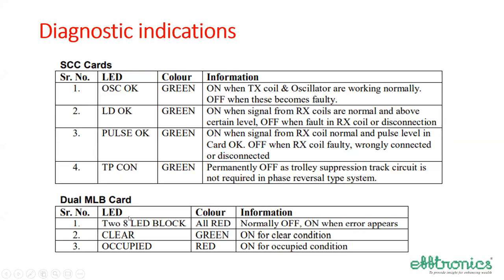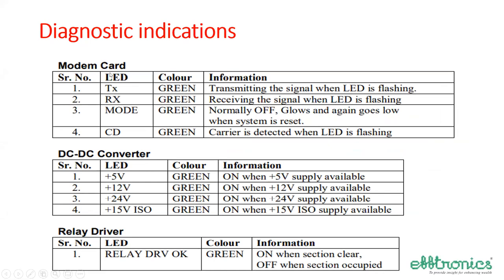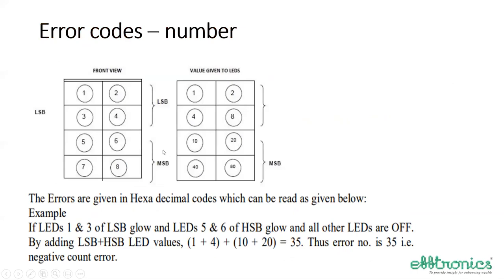Similarly, these are the microprocessor cards: modem card, DC-DC converter card, relay driver card. Some of them say the condition, some of them say about the faults, some both. Errors are given not in digital numbers, but through LEDs. And each LED has a value when it is lit. For example, there are 8 LEDs, and some of them are lit. When the third LED is lit, its value is 4. If the fifth LED is lit, you have to consider it as 10. And these values are added, and then the number is arrived at.